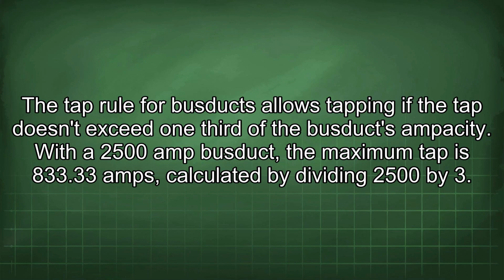The tap rule for busducts allows tapping if the tap doesn't exceed 1/3 of the busduct's ampacity. With a 2500 amp busduct, the maximum tap is 833.33 amps, calculated by dividing 2500 by 3.